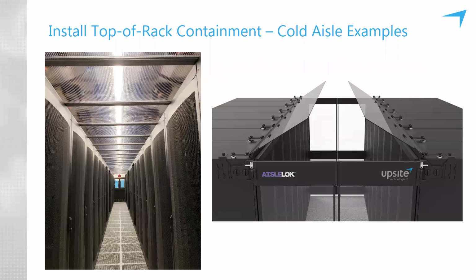All right, thanks, Lars. So I'll talk about the one on the right. So this is your capped aisle in a cold aisle containment solution. So you're looking at a long aisle here. It's 20 cabinets on each side. They're wide cabinets. They're 32 inches wide each. The real nice feature for capping an aisle is cabinets that are the same height throughout the aisle on both sides. And if you don't have that, and if you've got that kind of skyline profile, there are easy ways to accommodate and end up with the same result.